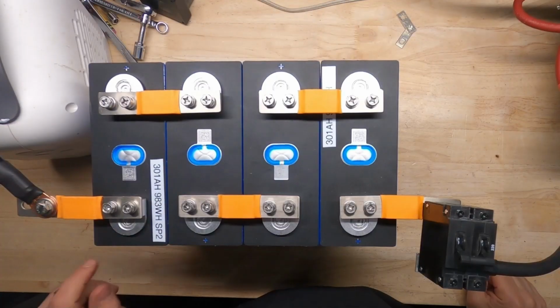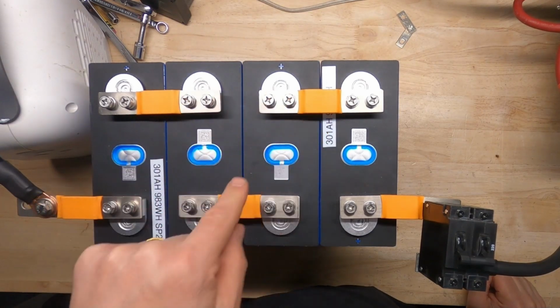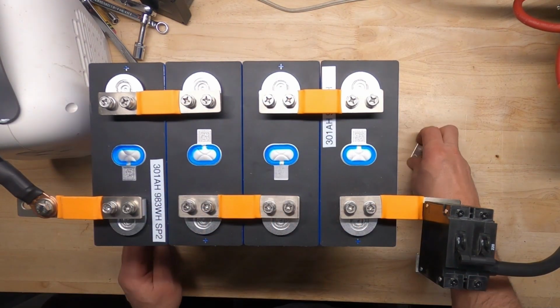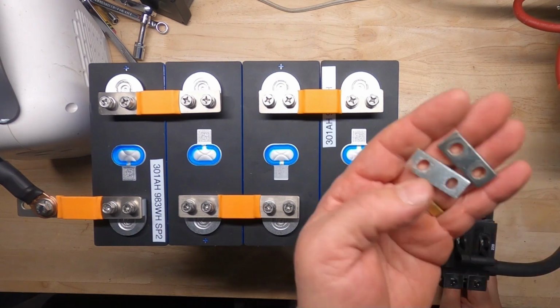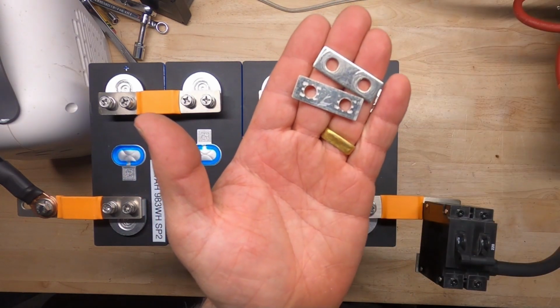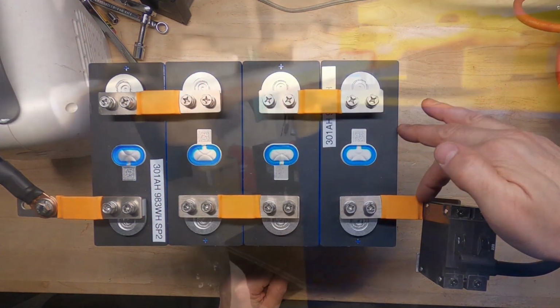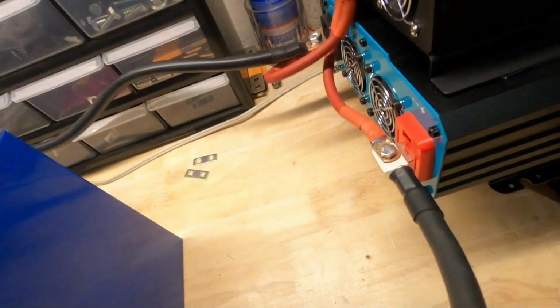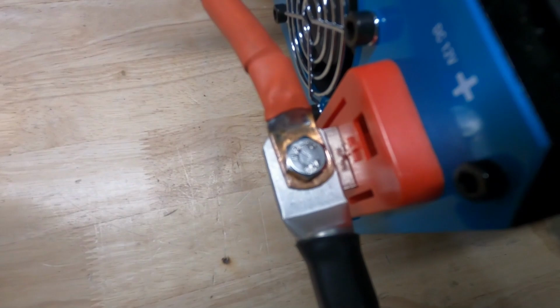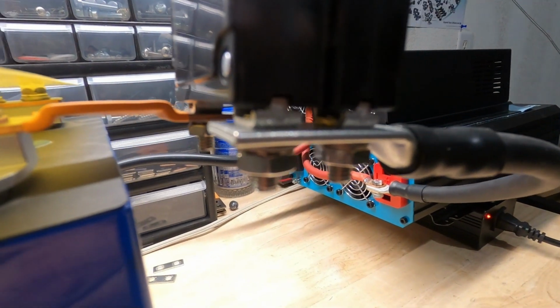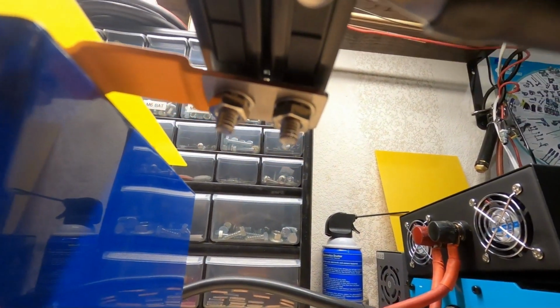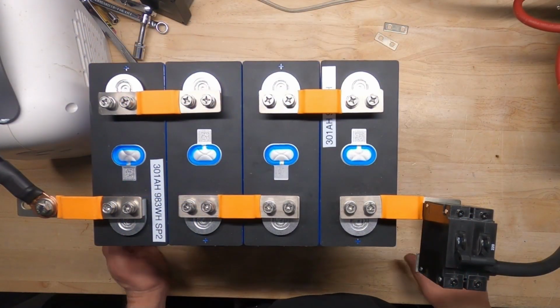Everything's been reconfigured. Let's check it out. We have flexible bus bars on all our battery connections. On the breaker, I removed the two bridge pieces of metal, so it's direct contact with the bus bar here. I flipped the cable around, the 50mm cable. The single hole lug is on the BMS side, or the inverter side, and the double hole lug is on the breaker side in direct contact with the breaker itself. So no more metal plates.